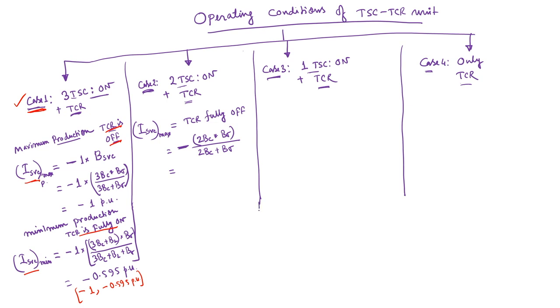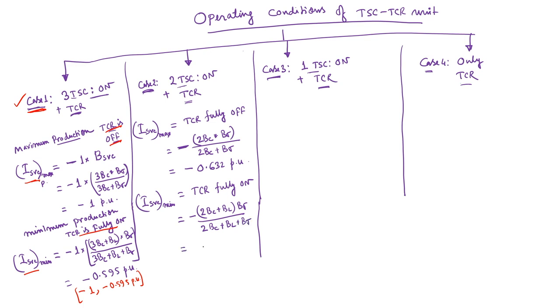So if you solve this, it will come out to be -0.632 per unit. Similarly, ISVC min corresponds to TCR fully on. So this is equal to -2BC plus BL multiplied by B sigma divided by 2BC plus BL plus B sigma. If you put all these values, as per my calculation, it comes out to be -0.27 per unit.